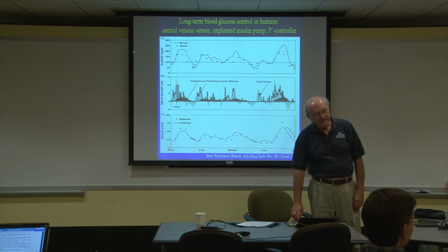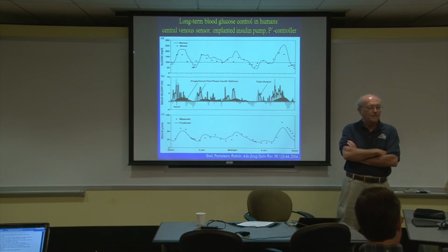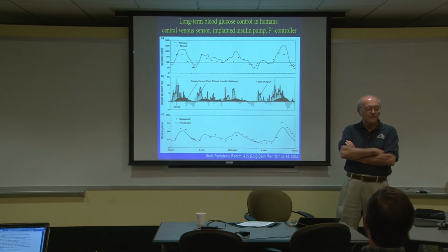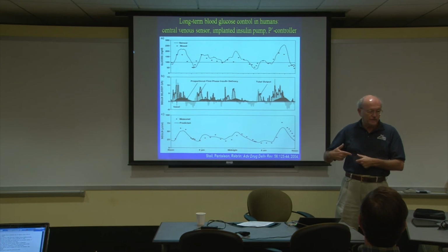On this slide, is there a fixed volume of insulin in the pump, or is it coming from an external reservoir? It's totally internal, and it's refilled every 3 months. So does that mean it's an invasive surgery to refill that? No, you use a needle, and you have to go into the clinic, and there's a nurse who knows how to do this. They punch through, it's just below the surface, and there's a rubber target there, and they punch through that rubber target, and then they fill it in, right?